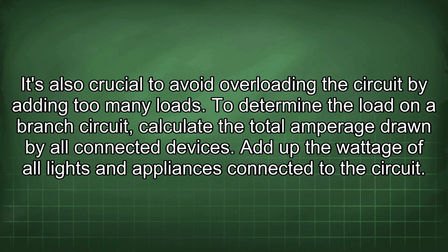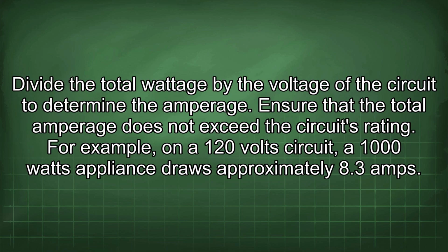To determine the load on a branch circuit, calculate the total amperage drawn by all connected devices. Add up the wattage of all lights and appliances connected to the circuit. Divide the total wattage by the voltage of the circuit to determine the amperage. Ensure that the total amperage does not exceed the circuit's rating. For example, on a 120-volt circuit, a 1000-watt appliance draws approximately 8.3 amps.